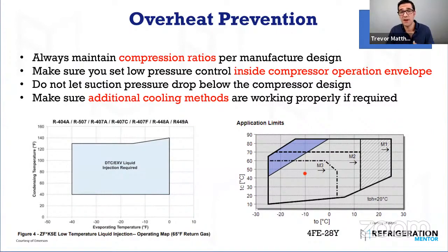And if you run it like that for a long period of time, it causes wear and you reduce the life of the compressor. So set the low pressure, learn how to set up a low pressure control properly to the compressor manufacturer's envelope. If suction pressure drops real bad, add additional cooling. Do you need to add injection to the compressor? Head cooling fan? And with these new refrigerants, 448, 449, all these new refrigerants that run way hotter than R22, 404, you need to check with the manufacturer. Do I need injection? Do I need a head cooling fan?